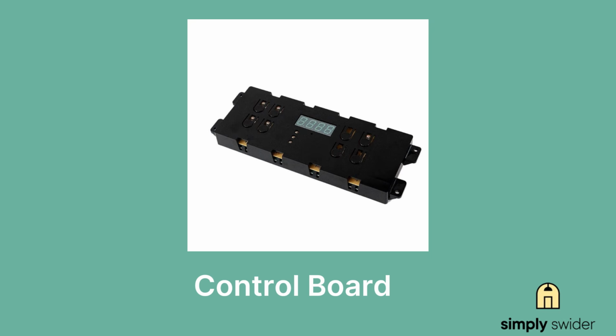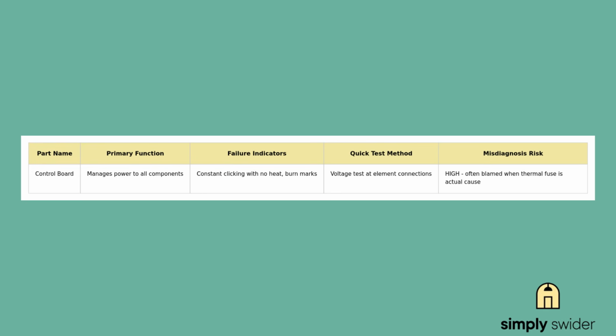Control boards are the pricey ones, anywhere from 140 to 235 for a complete replacement. Here's where you've got to be careful though. Control boards get blamed for a lot of problems that are actually caused by other components. I see people replace a perfectly good board when the real problem is a blown thermal fuse. Before you drop that kind of money, make sure you've tested everything else first.